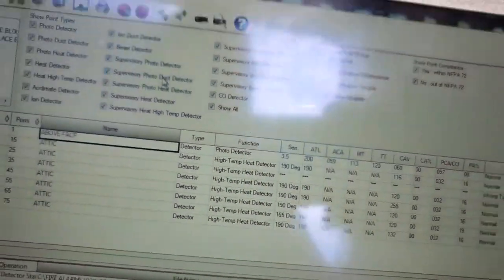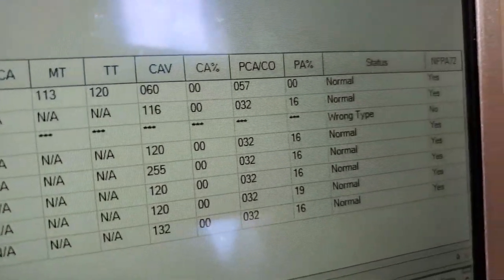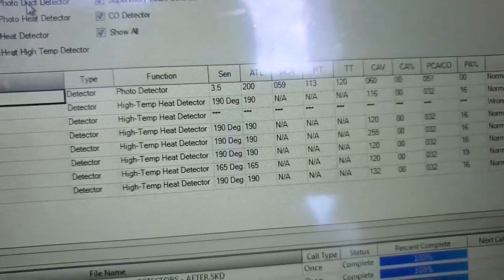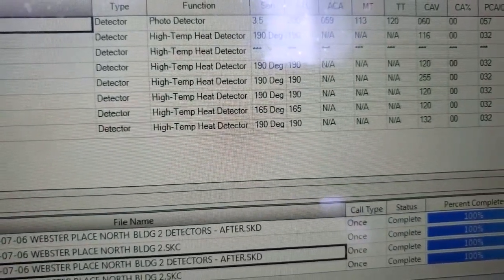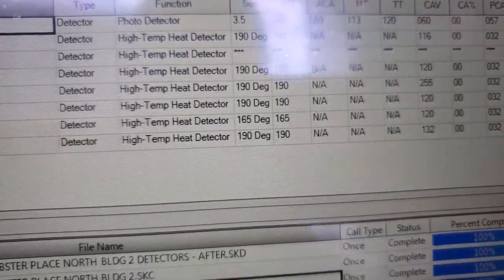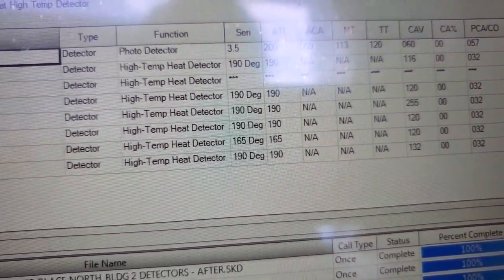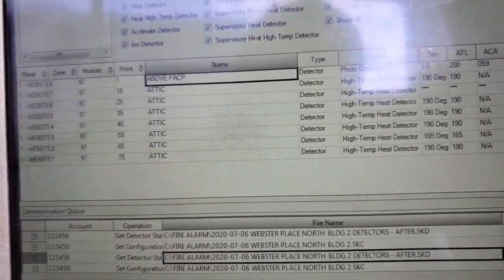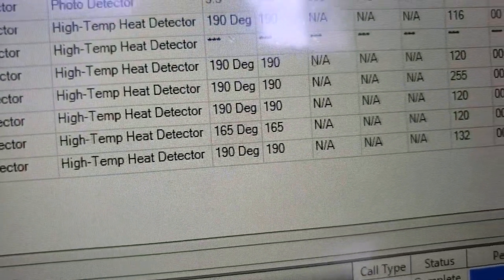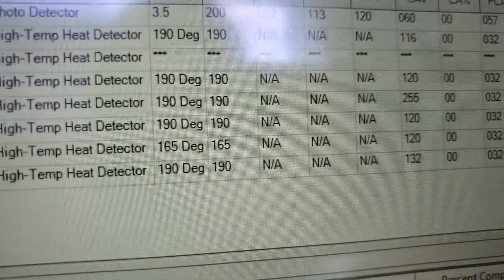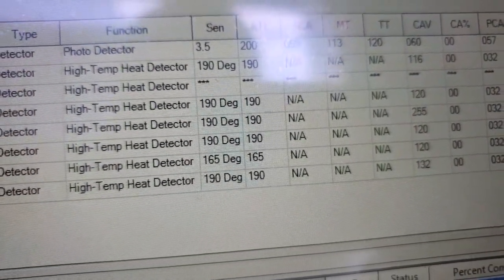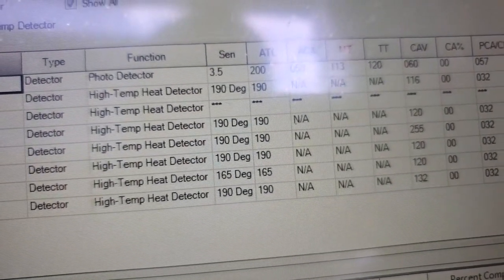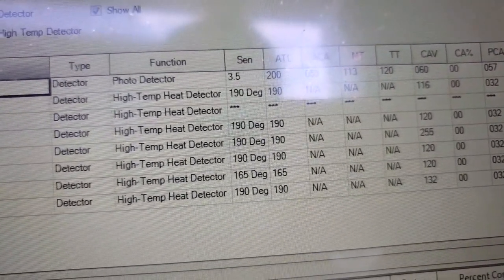I changed them all to 190, but just for kicks, I left one of the software zones. I changed all of them to 190 except for this one I left at 165. So with the high temperature detector, it says 165 and the ATL is 165. So apparently that column only applies to high temperature heat detectors.